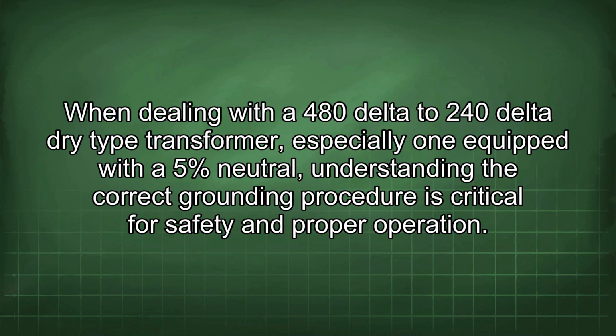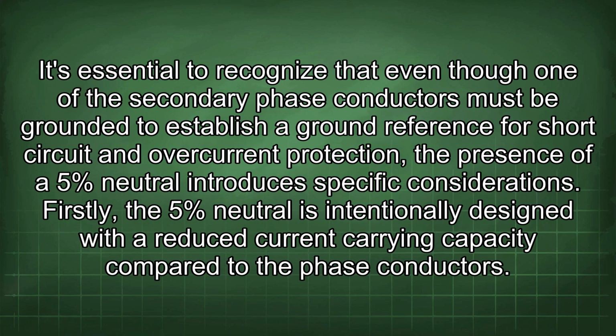When dealing with a 480 delta to 240 delta dry type transformer, especially one equipped with a 5% neutral, understanding the correct grounding procedure is critical for safety and proper operation. It's essential to recognize that even though one of the secondary phase conductors must be grounded to establish a ground reference for short circuit and overcurrent protection, the presence of a 5% neutral introduces specific considerations.